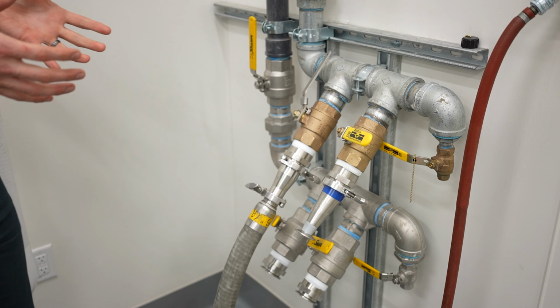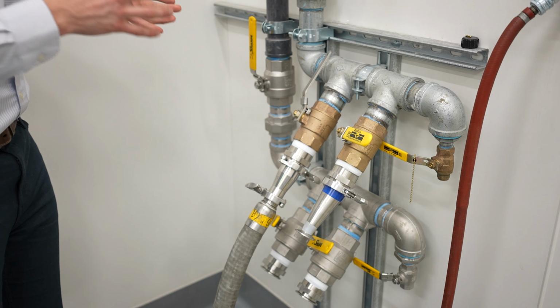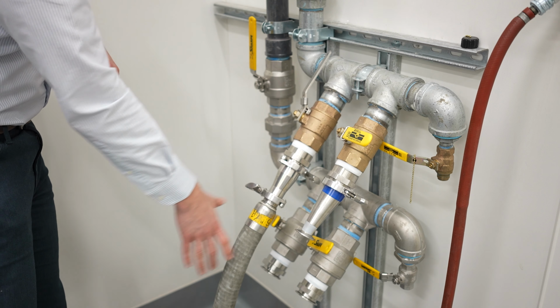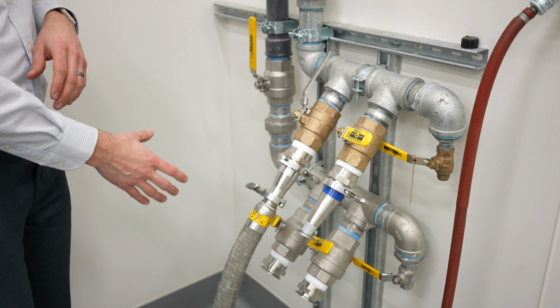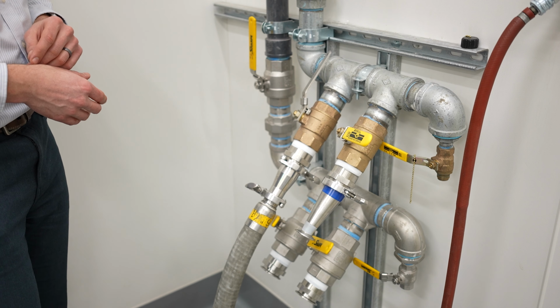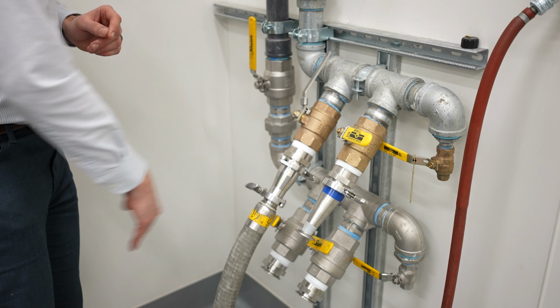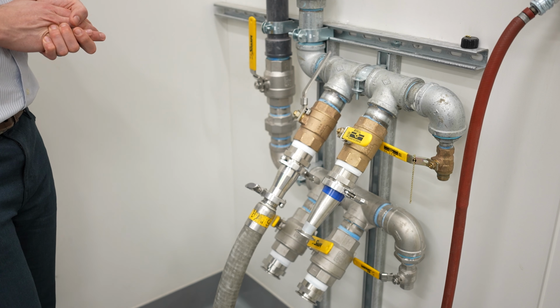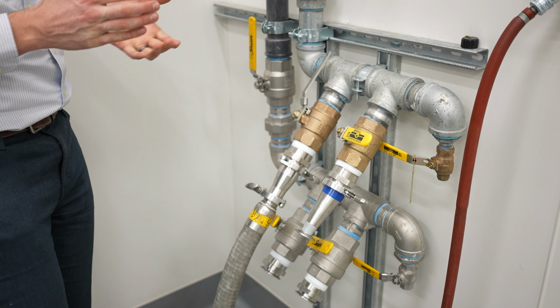So we just ran our baseline cycle. Now you're looking at our water supply for our cabinet washer. The supply on the left here is the valve to the cabinet washer, the water supply. This is the water that's filling up the cabinet when we open that water fill valve. And you can see it's fully open. So we have a pretty good sitting water pressure here, and we get a pretty fast fill. That sump fills up in about 20, 30 seconds or so.